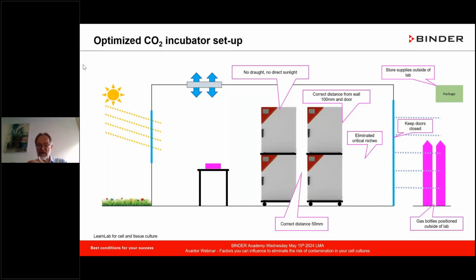The correct distance, 50 millimeters between CO2 units, regardless of tabletop or two stacks standing next to each other. CO2 is elevated from the floor - here you have different choices with and without casters, so here we're also reducing the risk of contamination. You have the adapter which allows you to actually sterilize the lower one by higher temperatures and continue to incubate in the upper one. So that is also something which helps good cell and tissue culture.